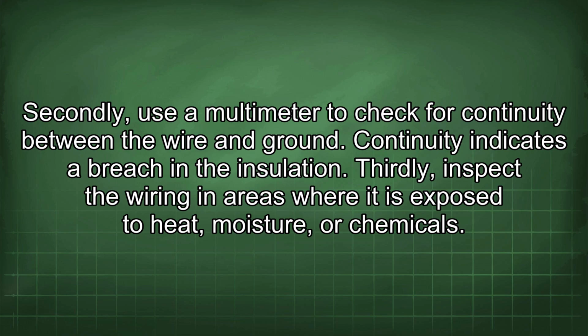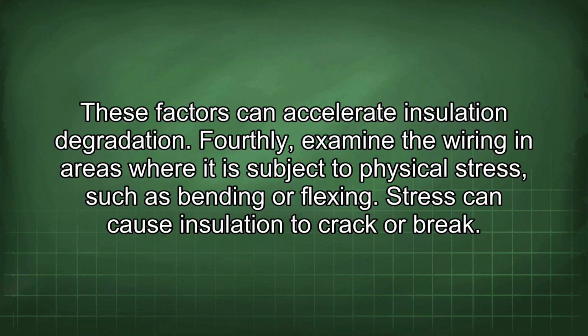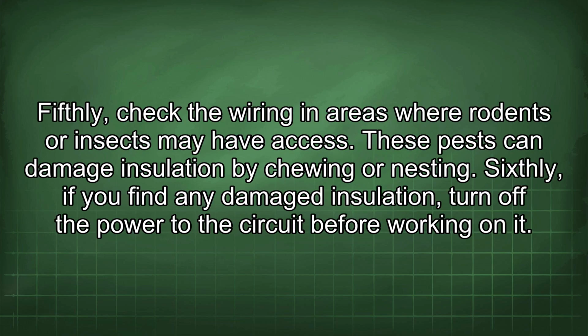Thirdly, inspect the wiring in areas where it is exposed to heat, moisture, or chemicals. These factors can accelerate insulation degradation. Fourthly, examine the wiring in areas where it is subject to physical stress, such as bending or flexing. Stress can cause insulation to crack or break. Fifthly, check the wiring in areas where rodents or insects may have access. These pests can damage insulation by chewing or nesting.